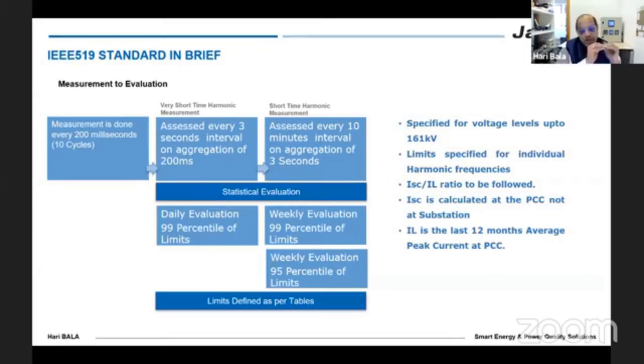Now, these limits are specified for different voltage levels. For example, if the voltage level of a customer is 400 volts, or 11 kV, 33 kV, 66 kV, and maybe up to 110 kV, we have different voltage limits. Then the limits are specified for individual harmonic frequencies as well, which means we know that limits are specified for the third harmonic, fifth, 7, 9, 11, and 13, but also for even harmonics in the whole picture. So these are complex calculations which we will have to go through.